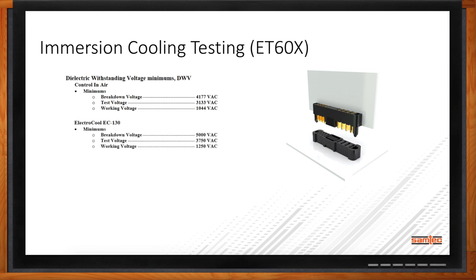Looking at the ET60X connector set again for DWV — dielectric withstanding voltage: the breakdown voltage in air is approximately 4,100 VAC, versus in ElectroCool you're looking at 5,000 VAC breakdown voltage — essentially 800 more VAC. So with both DWV and CCC, you're getting quite a bit more performance and capability out of a connector set when you look at it in an immersion cooled environment.